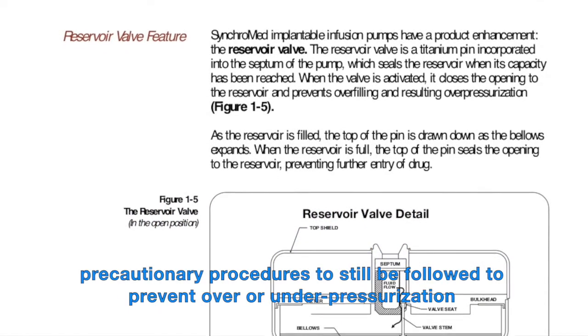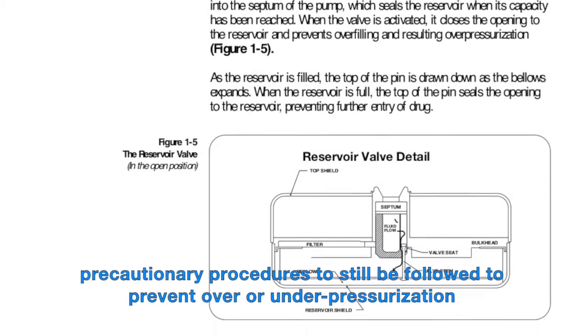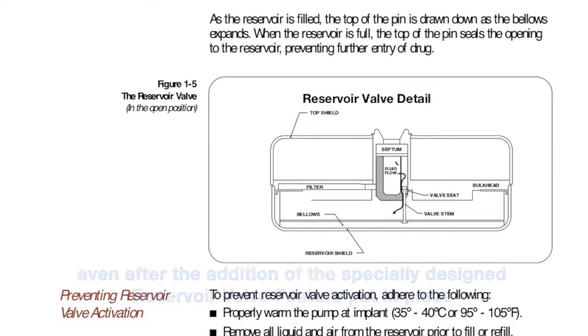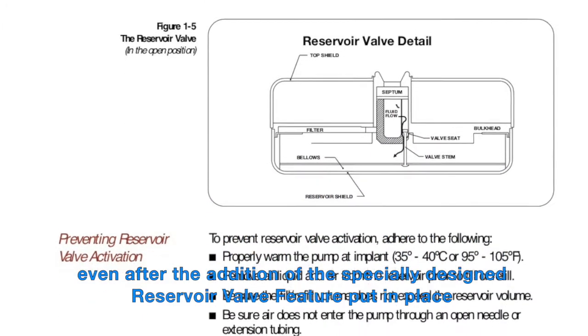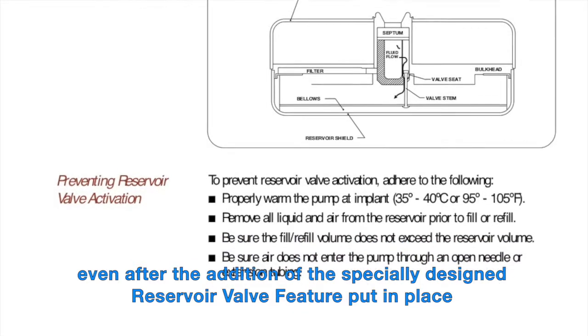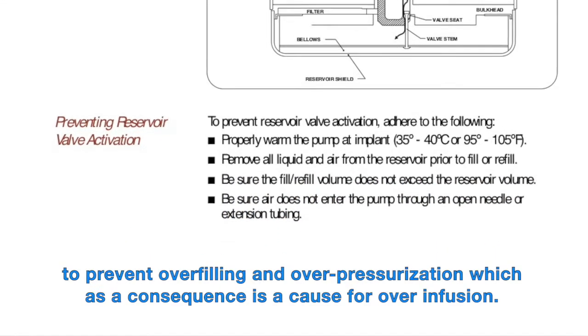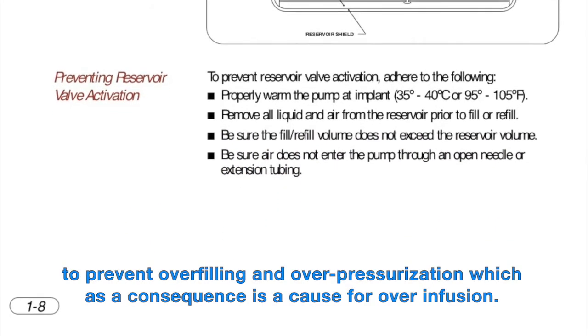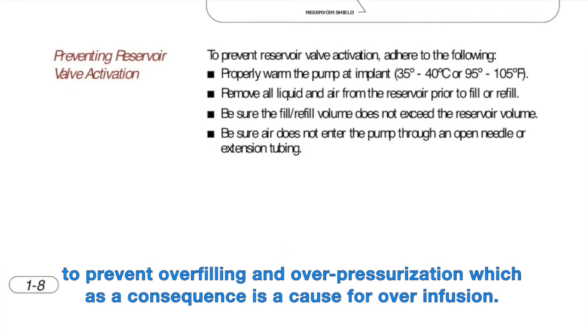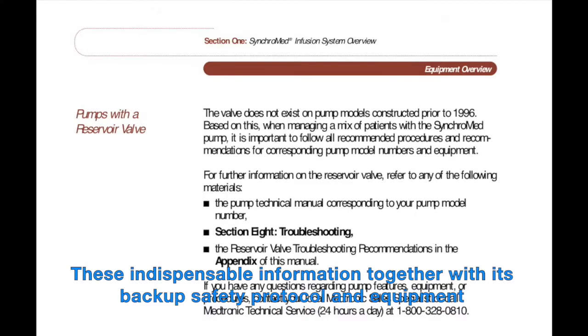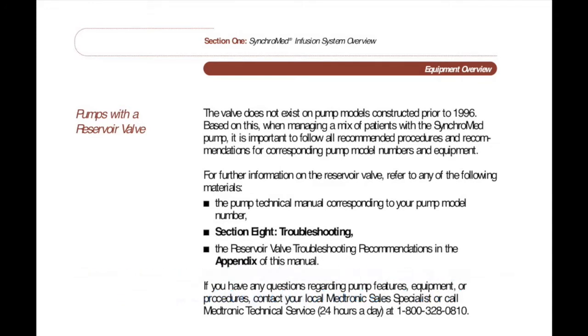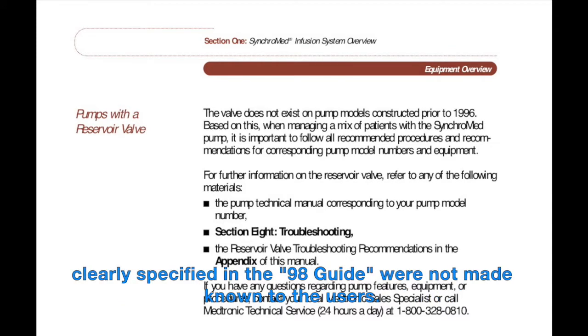Some of the other facts in the guide that this video will show is the need for distinct precautionary procedures to still be followed to prevent over or under pressurization, even after the addition of the specially designed reservoir valve feature put in place to prevent overfilling and over pressurization, which as a consequence is a cause for over infusion. This indispensable information, together with its backup safety protocol and equipment clearly specified in the 98 guide, were not made known to the users.